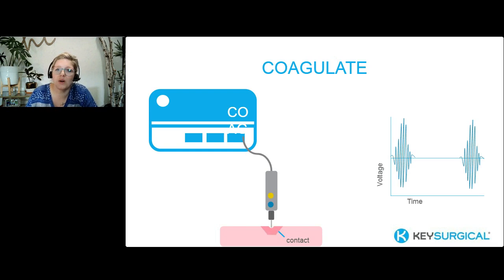So this is kind of that coworker who works for a little while and then takes a break, and works and takes a little break. And this current in the duty cycle is only flowing through the circuit about 6% of the time and off 94% of the time. So the voltage is higher for that shortened amount of time to compensate for those current changes. But coag is a contact technique. We're actually applying that electrode right to the tissues.